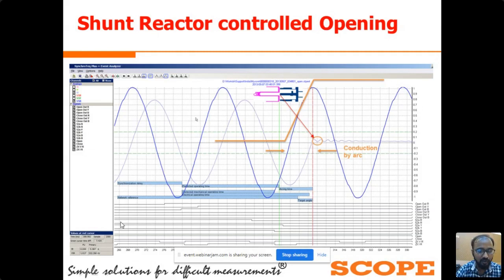Whenever the CSD receives the command from the TNC switch or from the SCADA system, it will hold the command and synchronize the circuit breaker operating time with the system voltage, and then it will execute the command. So you can see here, this is the synchronization time delay. After the synchronization delay, the CSD has executed the command to the circuit breaker. The CSD has synchronized the breaker operating time and calculated the moment to execute the command to the CB in less than 1 cycle, meaning less than 20 milliseconds. The CSD does all its calculation and executes the command to the circuit breaker.